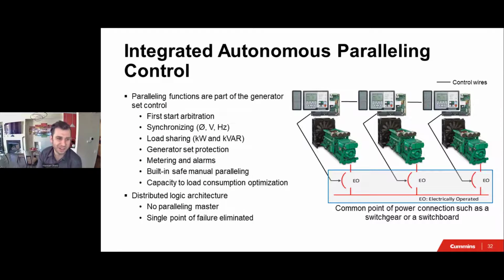With the integrated autonomous paralleling control, all the paralleling functions that I described are repeated on each and every generator. We need a point of common connection, and we run a few wires from one generator to another. This is what I described as distributed logic architecture, where the brains are repeated on every single generator. That means if one of the generators fails, its circuit breaker opens, it takes itself out of the equation, and the remaining generators continue like nothing happened.